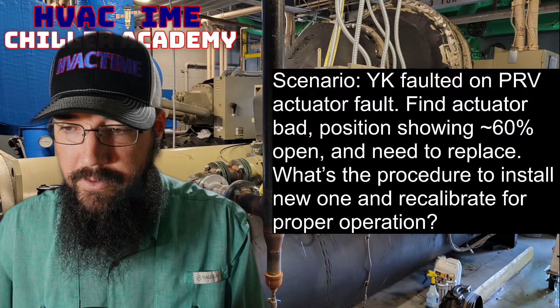What's the procedure to install a new one and recalibrate for proper operation? Okay, so installing a new actuator and then calibrating. What is really important for the installation procedure, one, the wiring in there can get a little tricky, and that's because of what the actuator can do. So it's more than just an open and close floating point actuator. That would be the style that actuator is. It's a floating point design.